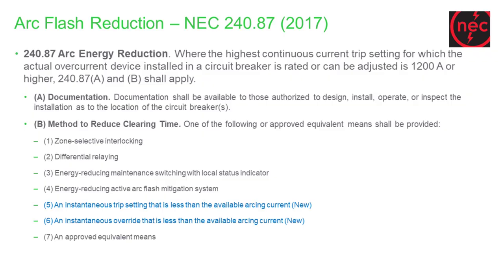Question: Which of the seven NEC 240.87B methods is represented by the light and pressure arc detection methods? The one we are using is the energy reduction active arc flash mitigation system — that's the method referring to arc sensor detection. That would be method number four.